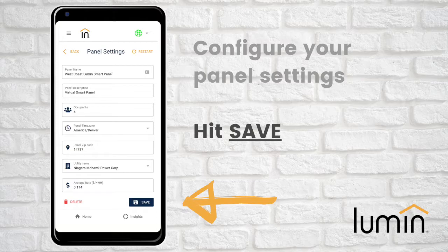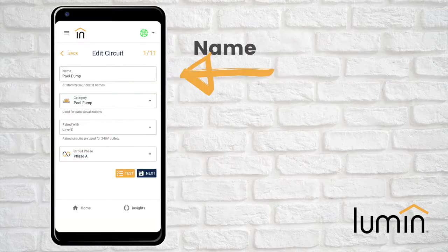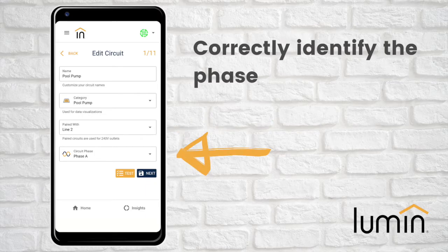Once all fields are completed, hit Save. You will now be prompted to configure each of your Lumin smart circuits. Please reference your Lumin circuit table and CT label to complete this step. For each line, enter a name, select the most appropriate category, and if the line is a 240-volt dual pole, pair it with the other line associated with the same circuit and make sure to correctly identify the phase.